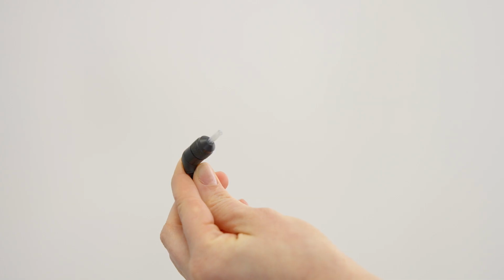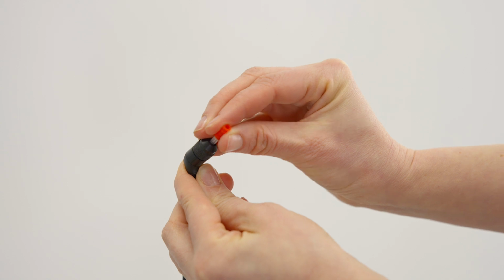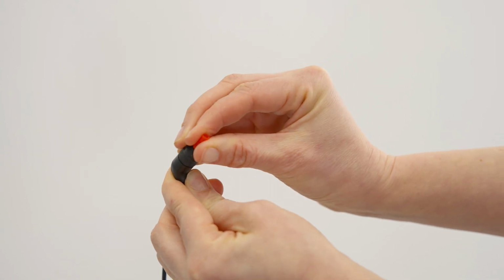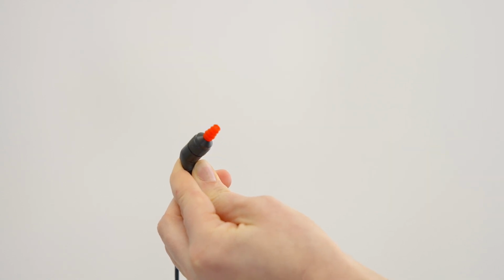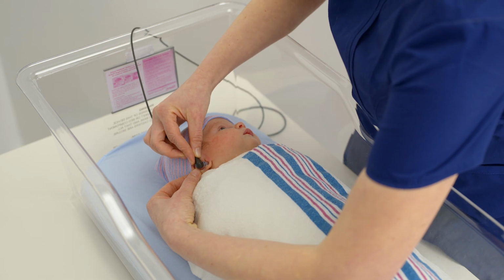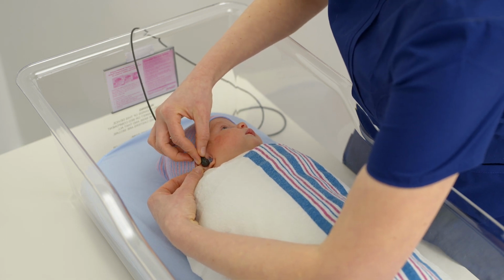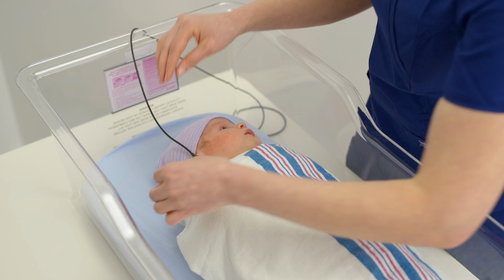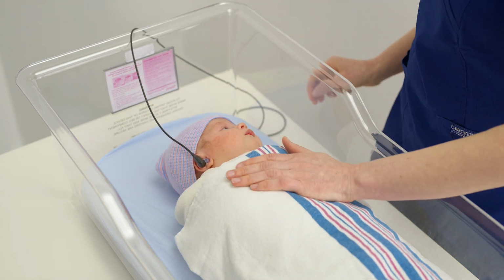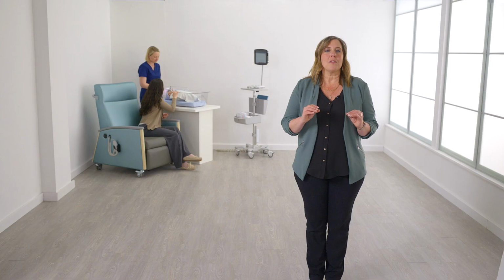When using the OAE probe, you must test one ear at a time. Choose the proper size ear tip based on your inspection of the size of the baby's ear canals. Apply the ear tips to the OAE probe. Insert the ear tip into the baby's first test ear by pulling down and out on the baby's earlobe to open the ear canal. Then aim and insert the ear tip gently but securely into the baby's ear canal. Release the earlobe and ensure that the ear tip is firmly in place and will not easily fall out.